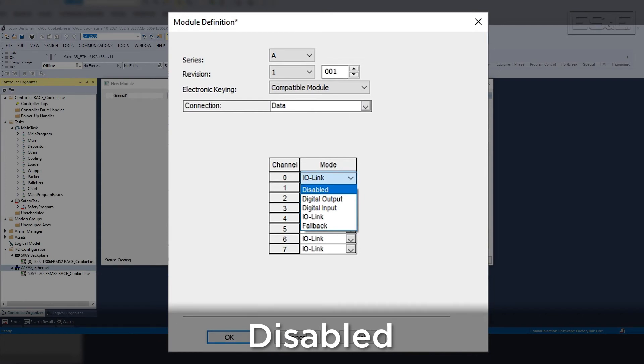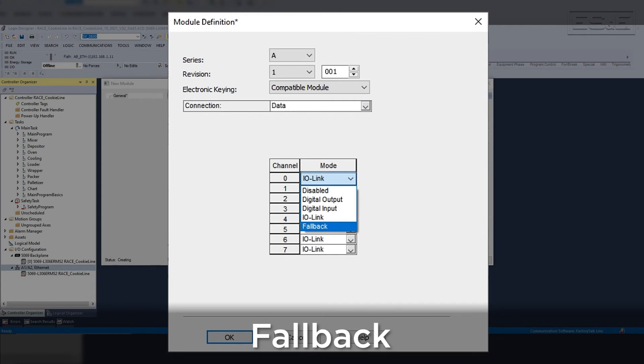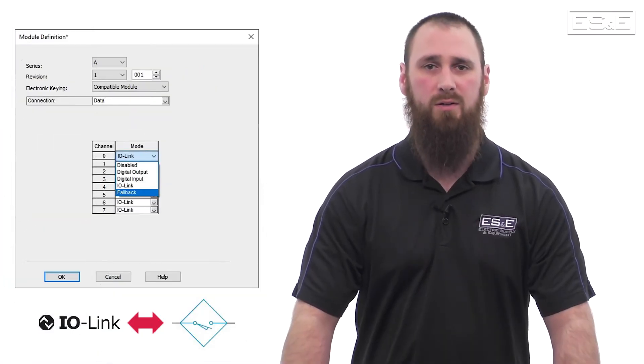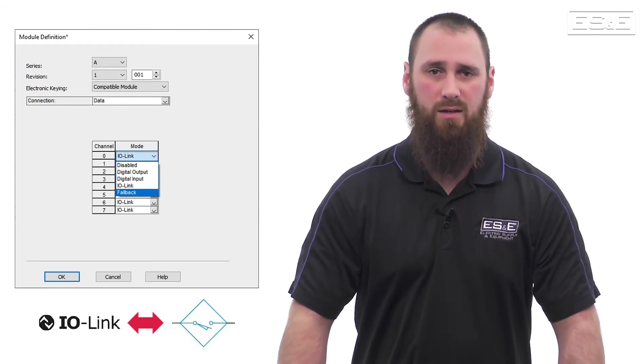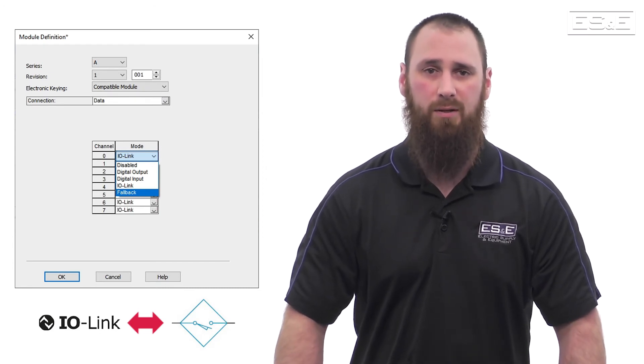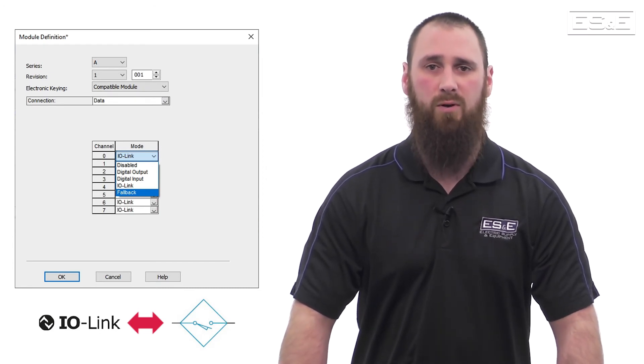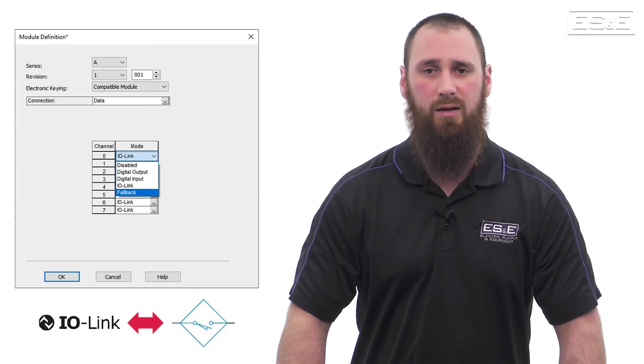The fifth and newest mode is called fallback. Fallback mode is a new feature released by Rockwell that allows the IO-Link Master to configure an IO-Link device, then instructs the device to behave like a standard digital input. This allows for increased response time on digital inputs while still having the ease of replacement IO-Link provides.